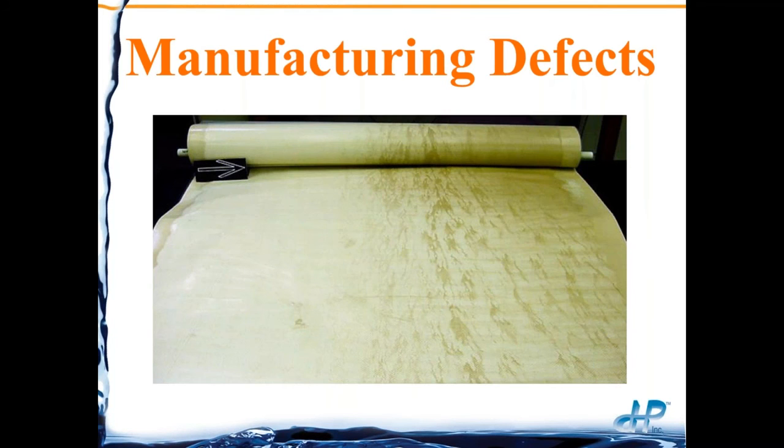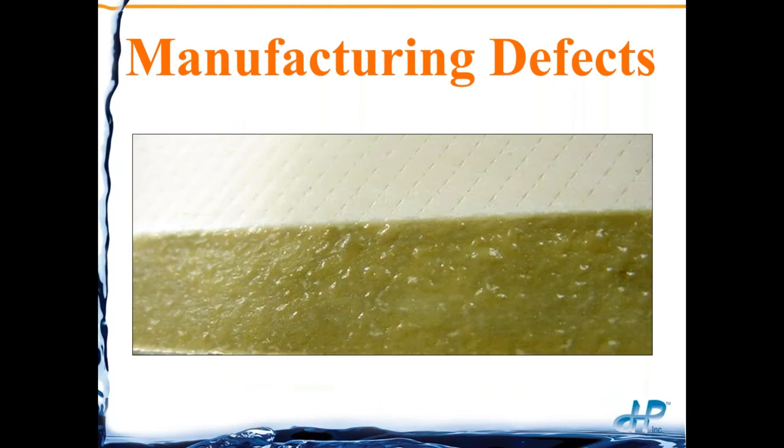Other manufacturing defects can be, of course, the chemistry aspect of the casting of the membranes themselves, as we see here. That's very, very uncommon to see. As far as I'm aware, that's the only time we saw this problem, was this particular element right here.